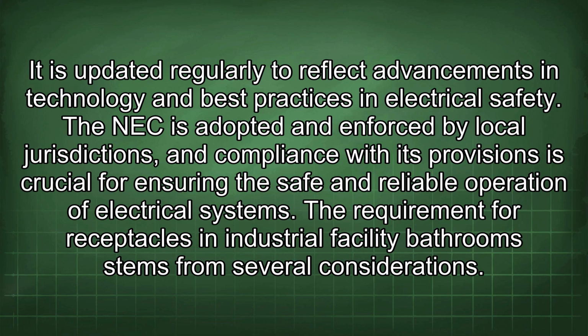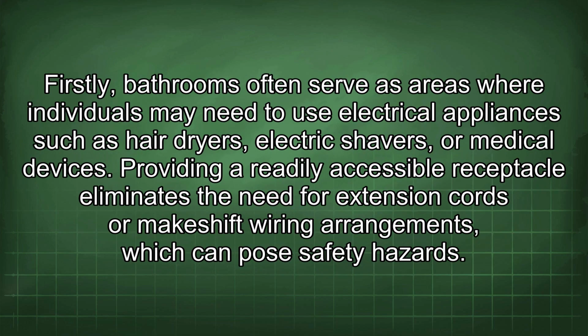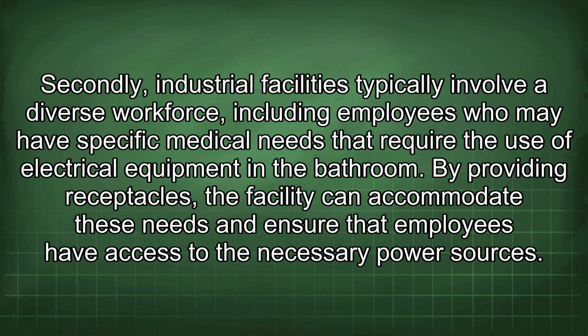The requirement for receptacles in industrial facility bathrooms stems from several considerations. Firstly, bathrooms often serve as areas where individuals may need to use electrical appliances such as hair dryers, electric shavers, or medical devices. Providing a readily accessible receptacle eliminates the need for extension cords or makeshift wiring arrangements, which can pose safety hazards. Secondly, industrial facilities typically involve a diverse workforce, including employees who may have specific medical needs that require the use of electrical equipment in the bathroom. By providing receptacles, the facility can accommodate these needs and ensure employees have access to the necessary power sources.